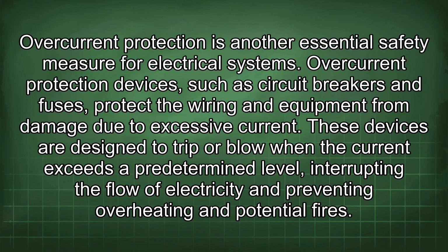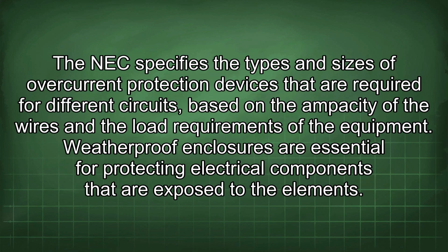Overcurrent protection is another essential safety measure for electrical systems. Overcurrent protection devices, such as circuit breakers and fuses, protect the wiring and equipment from damage due to excessive current. These devices are designed to trip or blow when the current exceeds a predetermined level, interrupting the flow of electricity and preventing overheating and potential fires. The NEC specifies the types and sizes of overcurrent protection devices that are required for different circuits, based on the ampacity of the wires and the load requirements of the equipment.